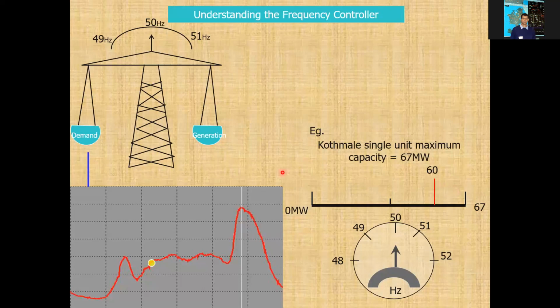Then what happened to the frequency? The generation side becomes heavier. Frequency goes up because now additional 40 megawatts have come to the system. The frequency control engineer notices that, and what he does is he reduces his output by 40 megawatts, so that once again the system frequency will be 50 hertz, and the frequency control machine is brought back to its mid region. So that is the activity that is happening day in, day out in the power system.